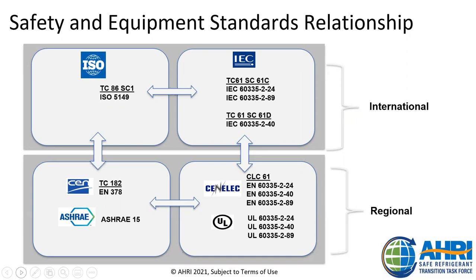Instead, there are US specific differences that are determined by the UL Standards Writing Committee, and it operates under the ANSI rules, just to be clear. These revisions are called national differences or national deviations and can be found clearly identified in the respective standards. In fact, these US national deviations are much stricter than the IEC standard, effectively making the HVAC systems that much safer. But because of this matrix of relationships, it also fulfills the World Trade Organization goals of breaking down technical barriers. So you may find that products made in other IEC adopting countries have pretty high standards of quality and performance similar to the US. Next slide.